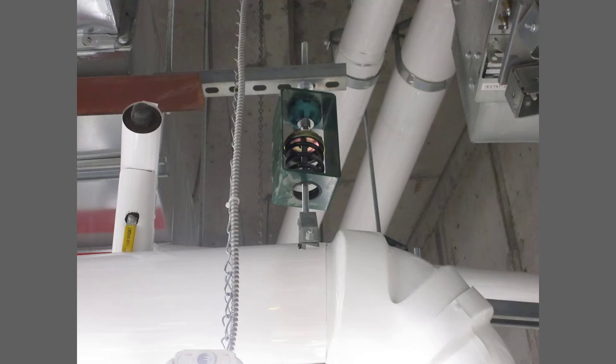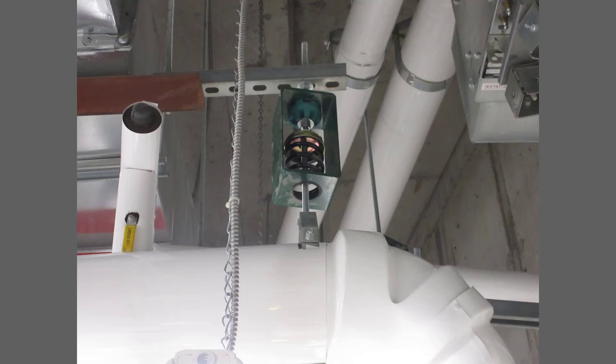I will say, however, that what the upper support rod is attached to looks a bit odd, since it's just a piece of Unistrut cantilevered away from a structural angle trapeze duct support, though since it is straight and appears solid enough, and not in our scope of work, there is no reason to raise any concern. This is an example of contractor creativity.